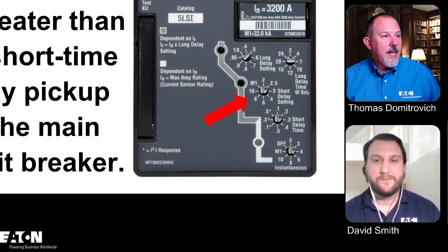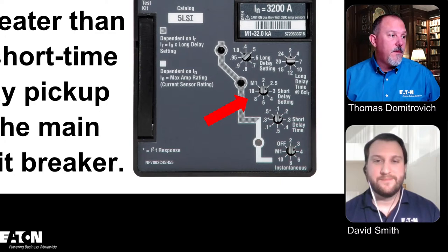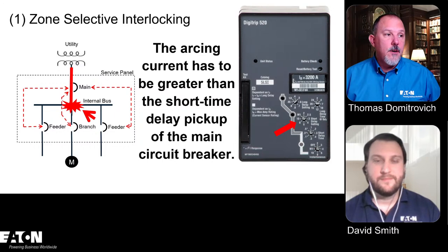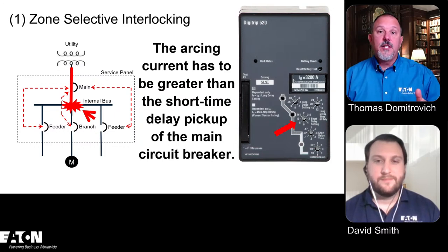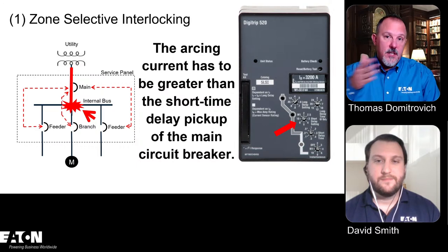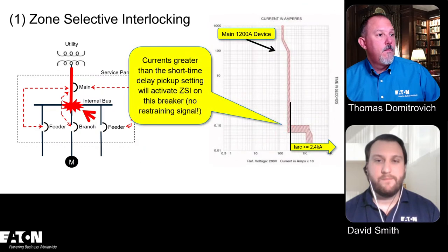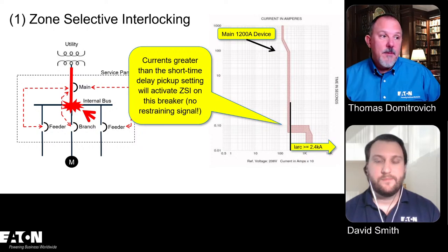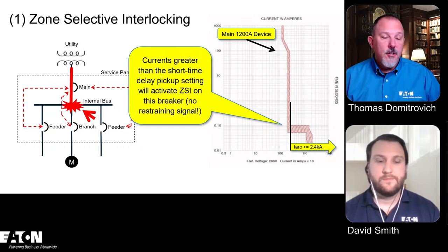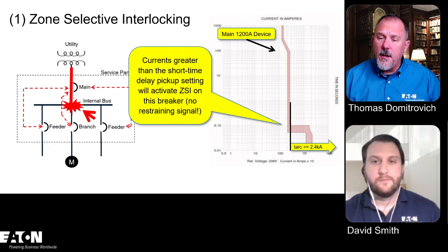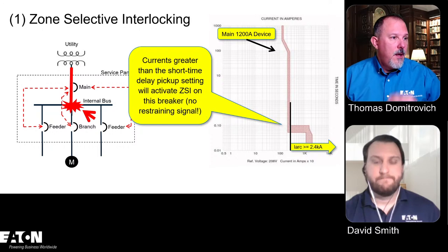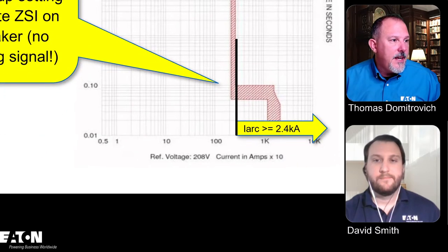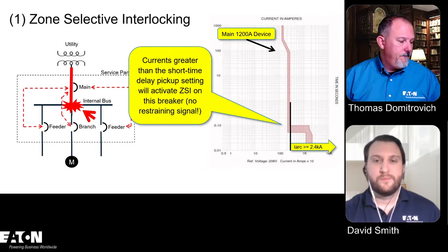So there's my short time delay setting, and that's from this application. That main breaker is going to trip based upon that short time delay. So whatever current that is set to, that is the current at which it will pick up. Got it. And there's your short time delay pickup. So any arcing current greater than 2,400 amps, which is based upon this trip curve for a 1,200 amp breaker, will have a clearing time, in this case around 0.1 seconds. But normally you can adjust that down.